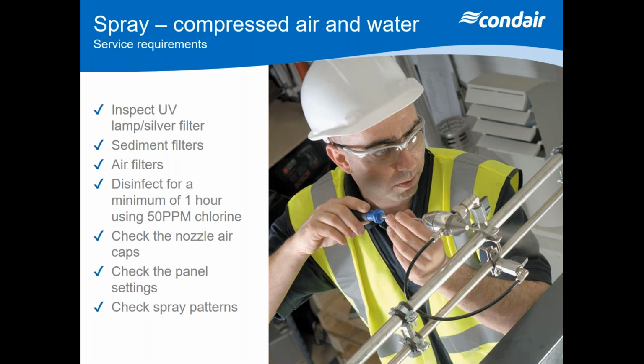Also, what you've got to understand is the nozzle. The nozzle will have a little bit of dust build up. The actual cap itself is Niflor coated to prevent any heavy scale build up, but you will get a certain amount of dust on the outside of the cap. So you physically need to go around and clean those caps at least once or twice a year, because if you don't, then you're going to find your spray patterns are starting to change and you'll get uneven spray. So that needs to be checked.